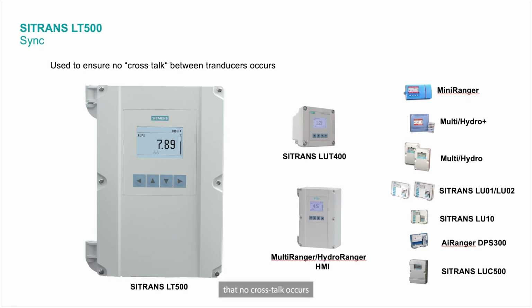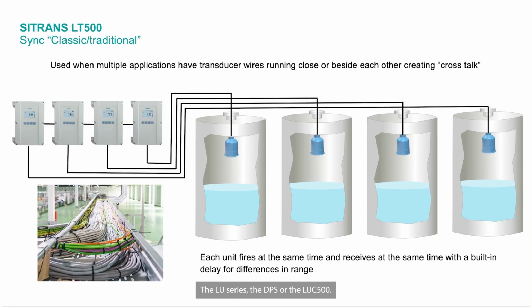Sync is used to ensure that no crosstalk occurs between multiple transducers when their cables are all run beside each other or very close. The sync function on the SITRANS LT500 can be used with any of our legacy portfolios such as the LUT400, the Multi-Ranger or Hydro Ranger HMI or classic models, as well as the Multi or Hydro Plus, the Mini Ranger, the LU series, the DPS, or the LUC 500.